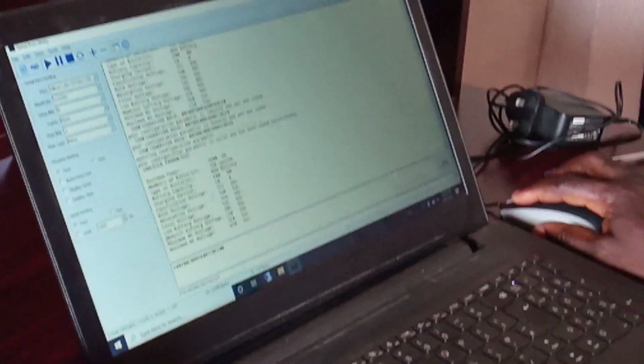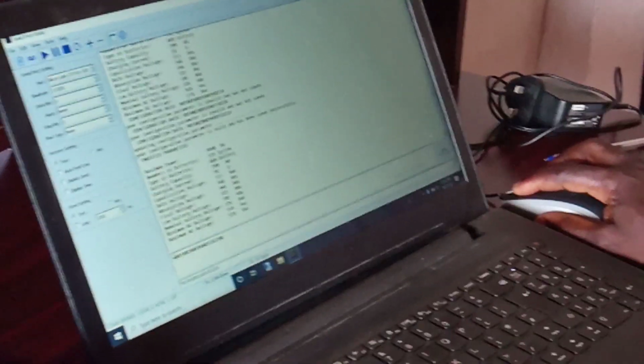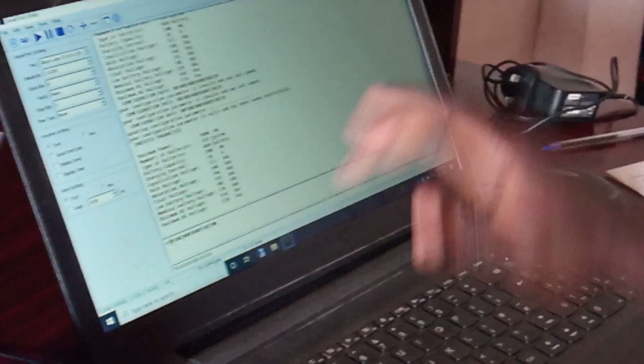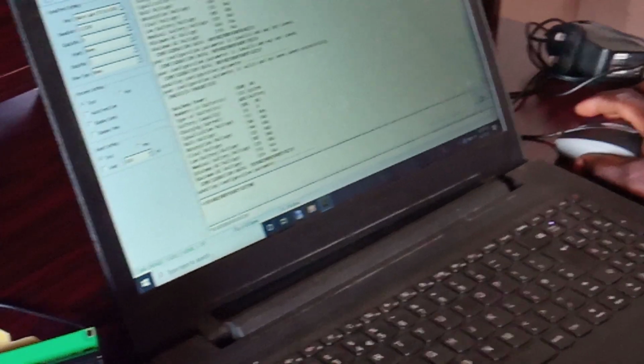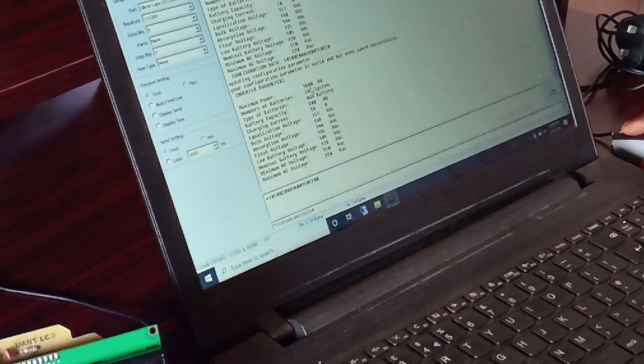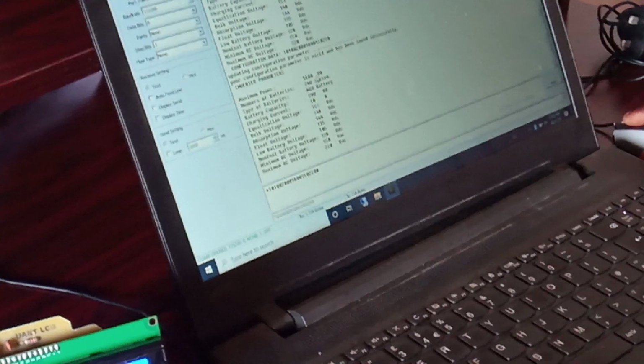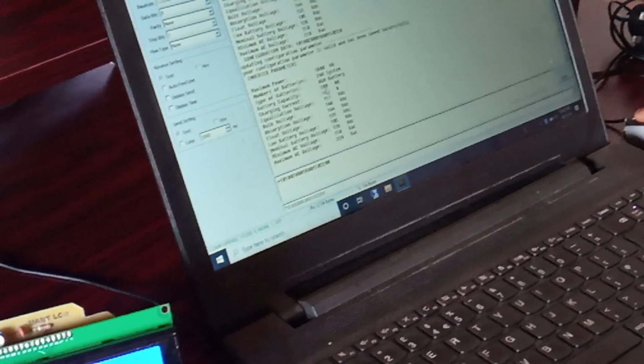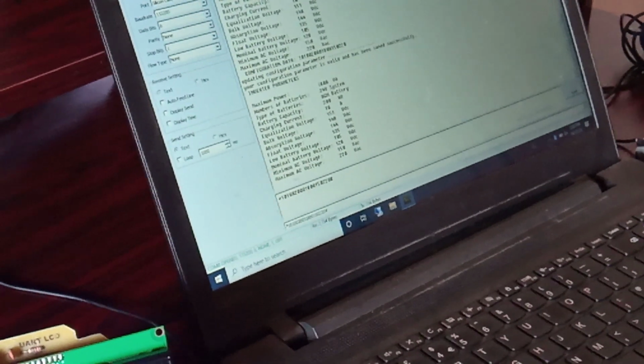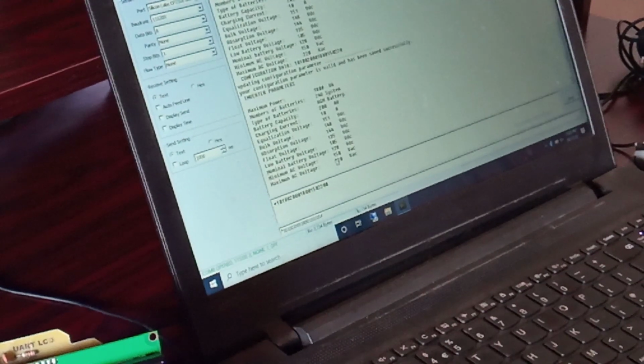Okay, let's say we are changing our 12 volt system to a 24 volt system. So I'll take the first parameter as 1. I'll save this. Okay, so it means that our inverter has been configured to run at 24 volt system at a power of 1800. The battery capacity is actually 200 amp hour. The charging current is 10 amps, and we said the minimum AC voltage we want to generate is 150. Then the maximum we want to generate is 220.